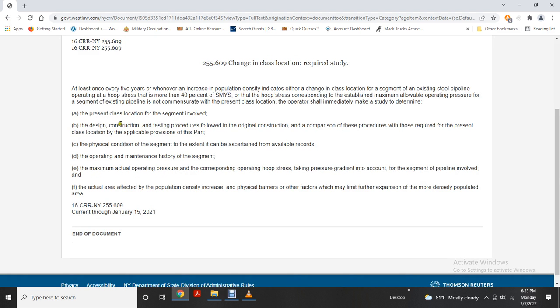Present location segment involved with the design, construction, testing procedure followed in the original construction, comparison with the procedures whose others required, present class location, applicable provision of this part, physical condition of the segment, the extent and certainty with available records, operation and maintenance history of the segment, maximum actual operating pressure and corresponding operating hoop stress, taking pressure gradient into account, segment of the pipeline involved, the actual area effect of the population density, physical barriers and other factors that may limit further expansion of more densely populated area.